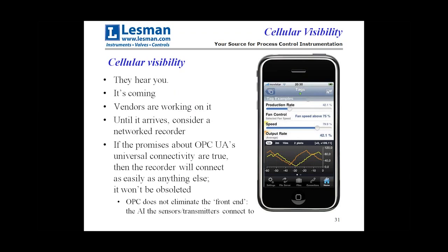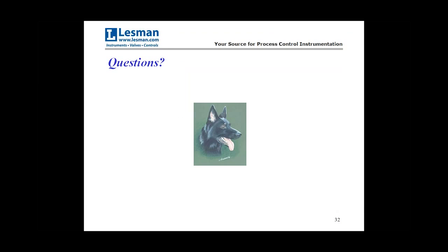People want cellular visibility — they want to see this on a cell phone. Our vendors hear that, they're working on it, and it's coming — but it isn't here today yet. So until that happens, you might really want to consider a network recorder. If OPC UA's promise about universal connectivity is really true, then the recorder will connect as easily as anything else and won't be obsoleted — because in the end, you still need something to hook the thermocouple or transmitter up to. None of the OPC stuff eliminates the front end that connects to the things in the field. So you can get on the bandwagon early and put the data on your desktop.